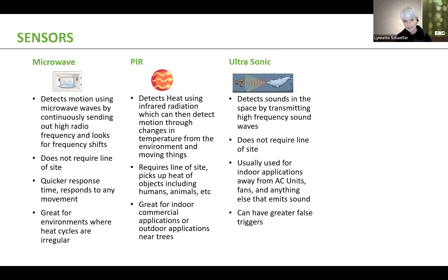Ultrasonic, on the other hand, detects sound in the space by transmitting high frequency sound waves. It also does not require line of sight, very much like microwave sensors. It's usually used for more indoor applications, but you have to make sure that you put ultrasonic sensors away from AC units, away from fans, anything else that emits any sort of sound because you can have major false triggers if you do that.